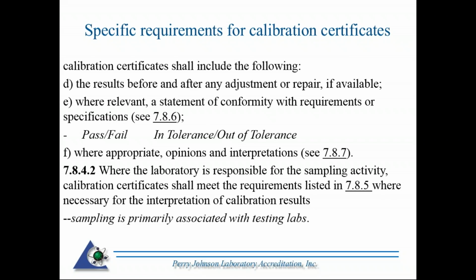Where relevant, a statement of conformity with requirements or specifications. Again, stating on a report, the customer wants a statement of compliance: pass, fail, in tolerance, out of tolerance, good, bad. Any of those things would be making a statement of compliance. And where appropriate, opinions and interpretations. There's a reference here to sampling. However, sampling is primarily associated with testing labs, but you can see this requirement, if for whatever reason it is carried over to the calibration labs, and I've yet to come across it, where the laboratory is responsible for sampling. Calibration certificates shall meet the same requirements, which we're going to go through here in section 7.8.5, necessary for the interpretation of the calibration results.